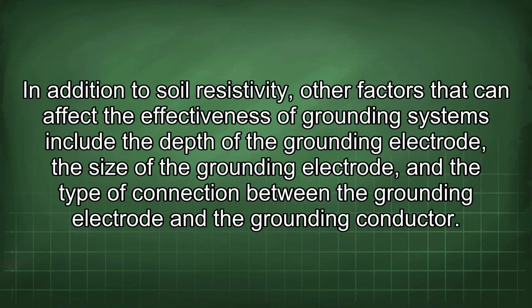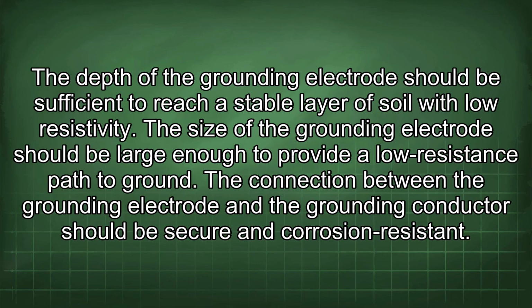In addition to soil resistivity, other factors that can affect the effectiveness of grounding systems include the depth of the grounding electrode, the size of the grounding electrode, and the type of connection between the grounding electrode and the grounding conductor. The depth of the grounding electrode should be sufficient to reach a stable layer of soil with low resistivity. The size of the grounding electrode should be large enough to provide a low resistance path to ground. The connection between the grounding electrode and the grounding conductor should be secure and corrosion resistant.